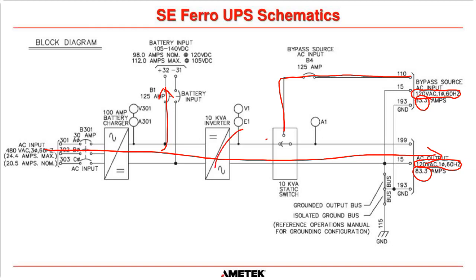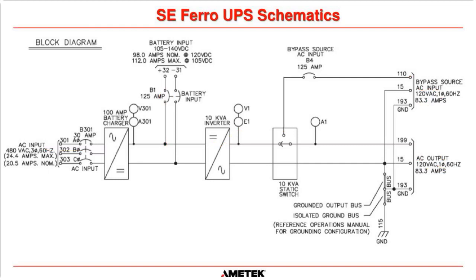Okay, and the bypass has to be able to supply the same current as the output, because if the inverter fails, okay, we are expecting the bypass supply to then feed power out to the load circuit. So if you had full load of 83.3 amps out of the inverter, then we have to be able to supply that from the bypass. So when sizing your cables out to your load circuits, we know that 83.3 amps is what we would expect at full load, and the bypass is going to have to supply that as well. So size your cables correctly for both of those amperages. And then we'll discuss this output bus arrangement later on when we go down to the schematics.